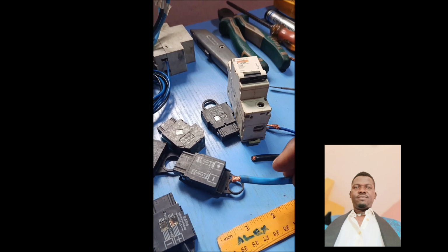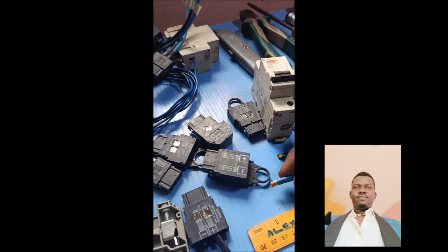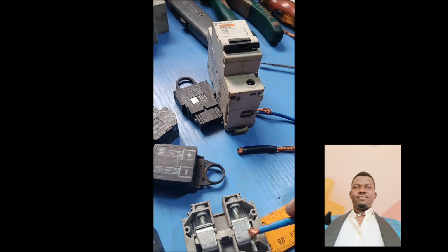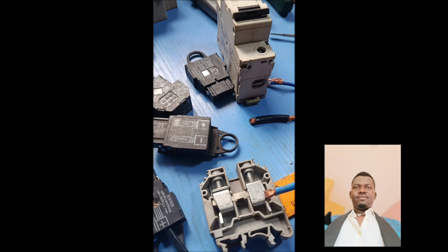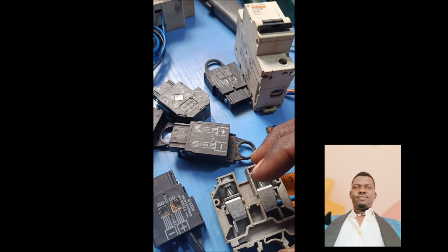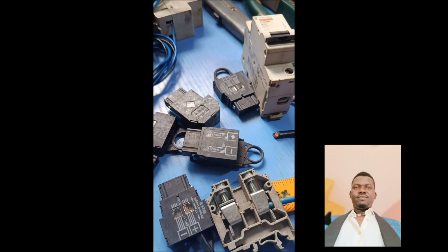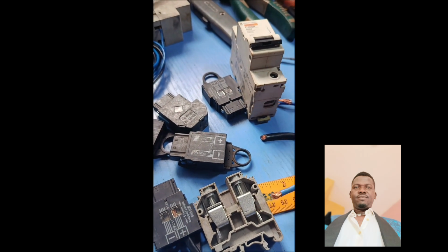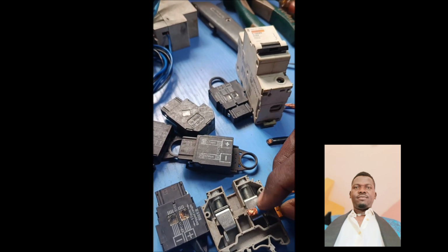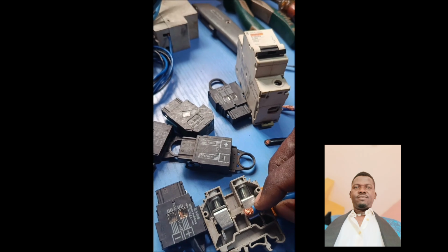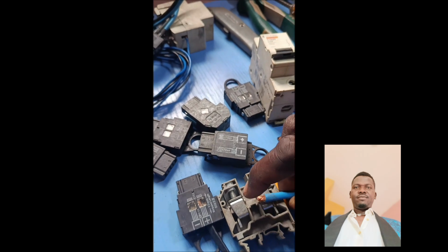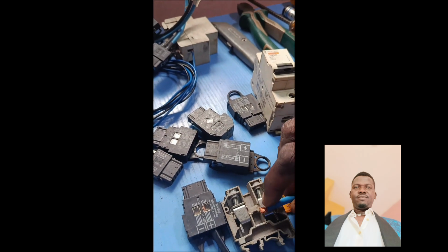So when you have a cable like this, when you tie, the insulator will be on the metal conductor, on the metal part of this. When you tie it, before you know it, partial contact will arise. This connector will burn. If you watch very closely, you see that it is very small. When you tie this screw, you find that it will be resting on this insulator. There is no electrical contact.